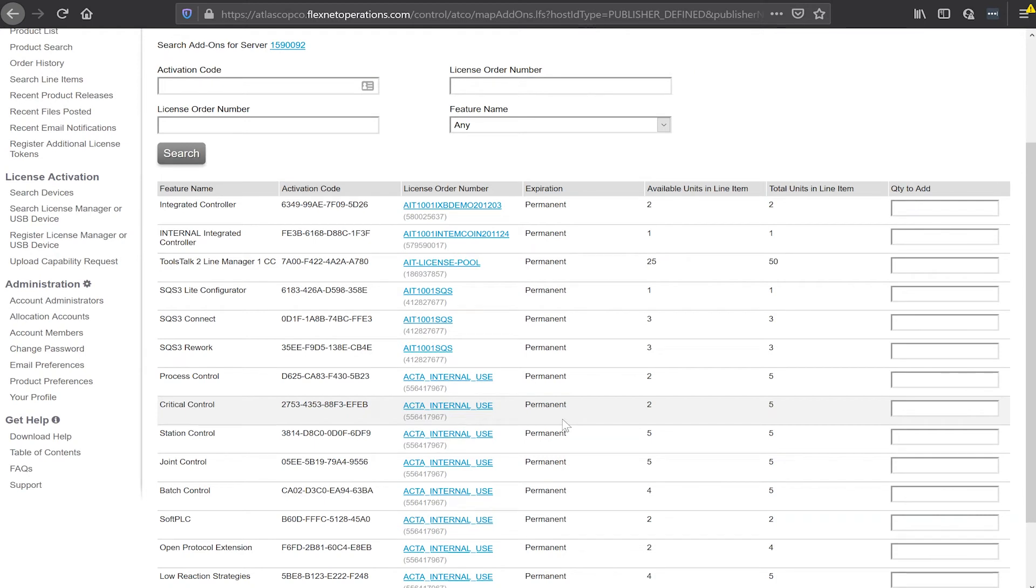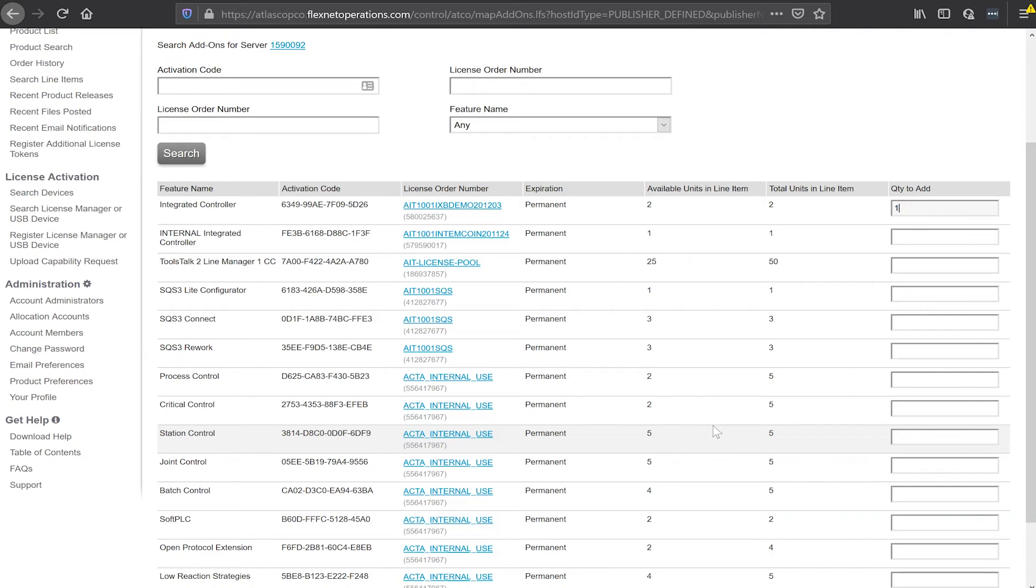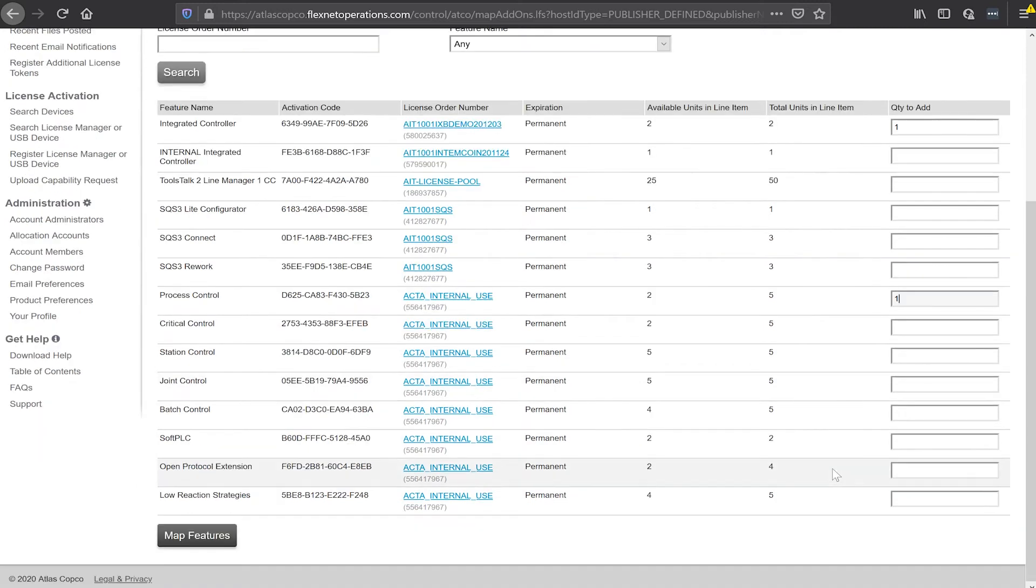There's two licenses we'll need to use the integrated controller on the ICB tool. We'll need an integrated controller license and then whatever different virtual station type that we want to use with this tool. For today we'll choose the process virtual station type and I will add that to this. I'll map these features to this device as well.